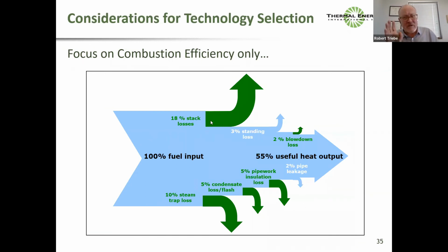So now I want to talk about kind of the lie. Some people would think, well, I'm going to go from steam to hot water, and I'm going to do hot water condensing. My efficiency can go up. I can tell you, I can get that thermal efficiency without converting from steam. You could keep your steam on a steam boiler. You could take your cold users and hook them up to the economizer, and now your thermal efficiency will be the same as a condensing boiler. You can get condensing boiler efficiencies with steam boilers by putting condensers on them, condensing economizers.